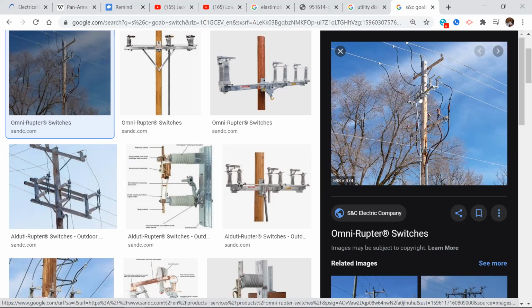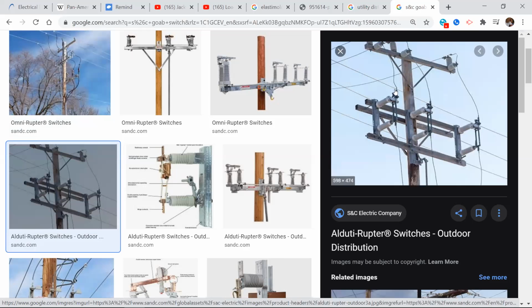Now, when you stand on the ground and open and close it, do you think the timing on this is exact for all three switches? The timing, the open or the close? Probably not. And I mean, when I say timing wise, how many cycles per second? 60. Yeah. So we're looking at 1/60th of a second. Something could go wrong in timing, especially when you start getting to switches of this nature that are much larger and bigger. Not all three are going to open, and not all three are going to close at the exact same time. All right, so when that happens, especially on the open, if two phases open and one phase is just a little bit behind in the schedule, let's go ahead and put this in another frame.